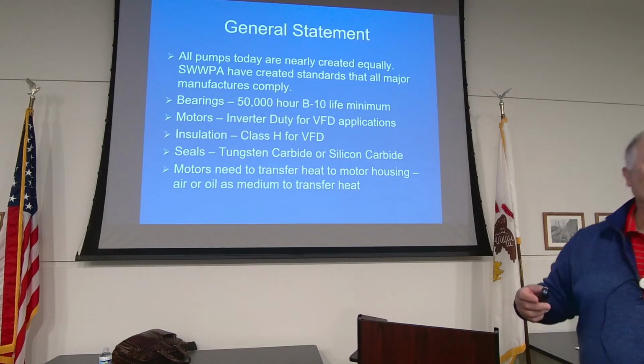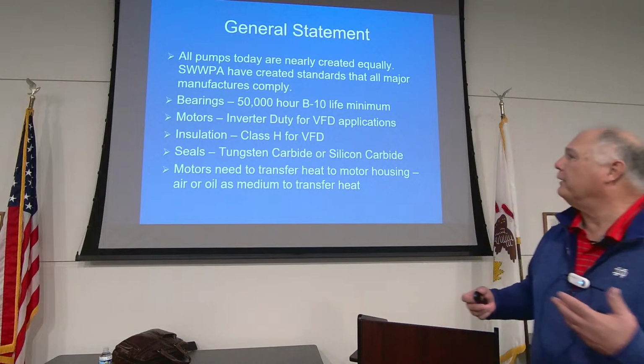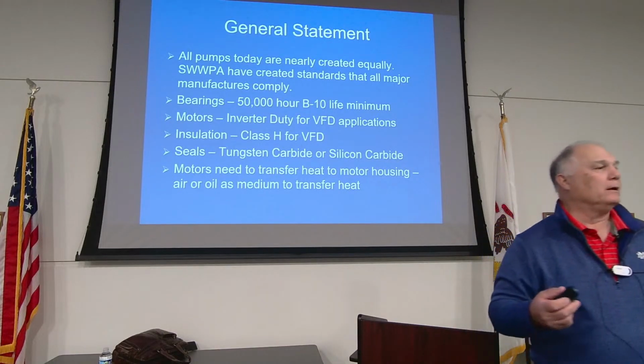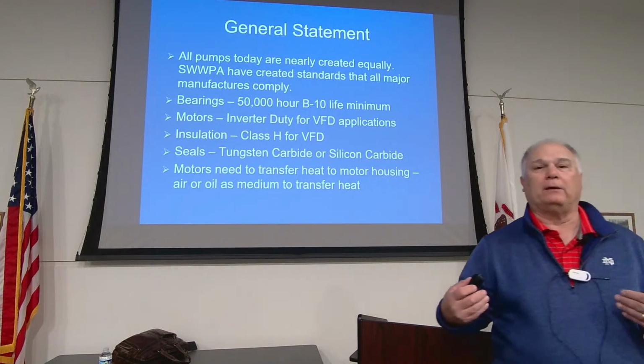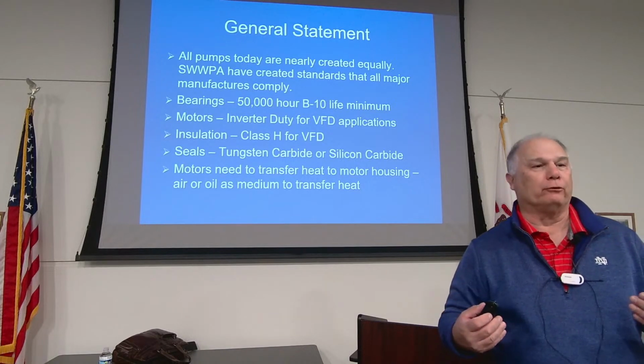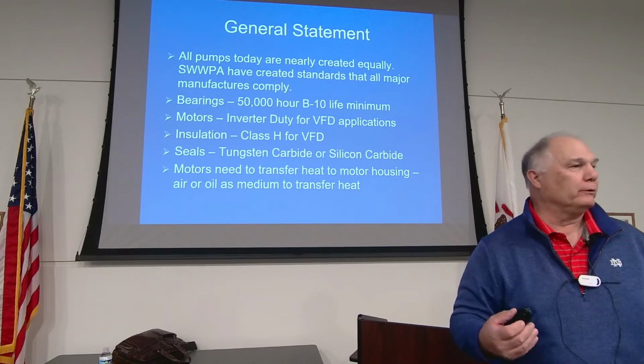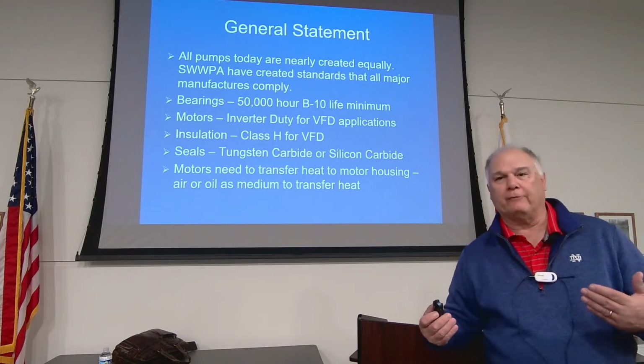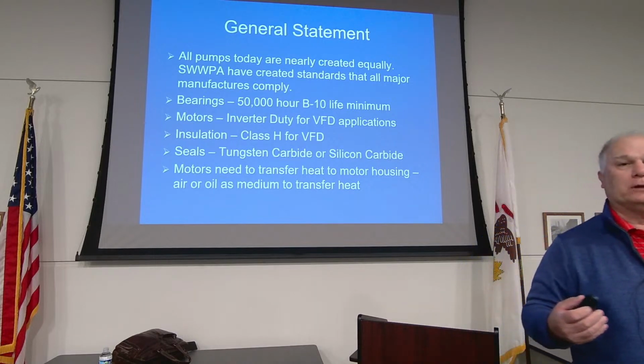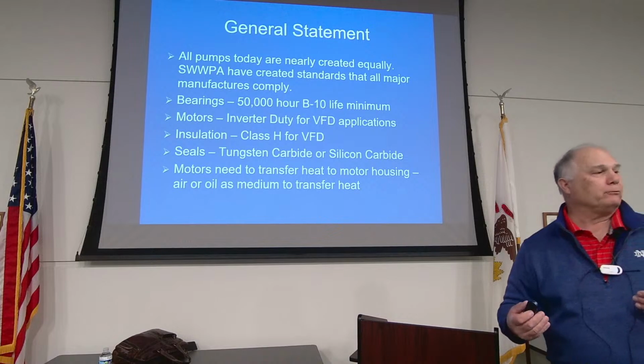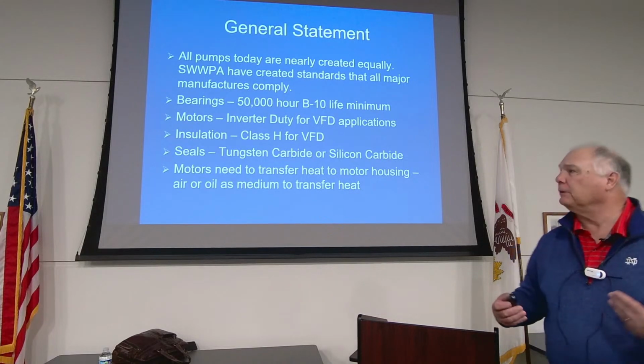So all motors are either going to be oil-filled or air-filled, but we've got to get rid of the heat. In today's world, back in the day, we didn't have everybody have inverter duty rated motors, which are VFD motors. Most motors today are all Class F or greater insulation, so you can hook them up to a VFD and operate them.